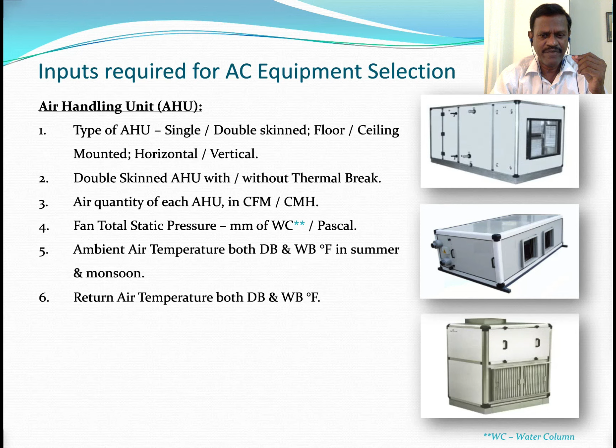Then the air quantity of each AHU in CFM or CMH you have to specify. Then fan total static pressure you have to mention in terms of mm of water column or Pascal. Then ambient temperature, that is for the fresh air you are going to take, so you have to specify the ambient dry bulb and wet bulb, both summer and monsoon. Return air temperature, both dry bulb and wet bulb. Then you have to specify all the sections you require in the AHU, like mixing box, filter section, coil section, fan section, etc., depending upon your requirement.